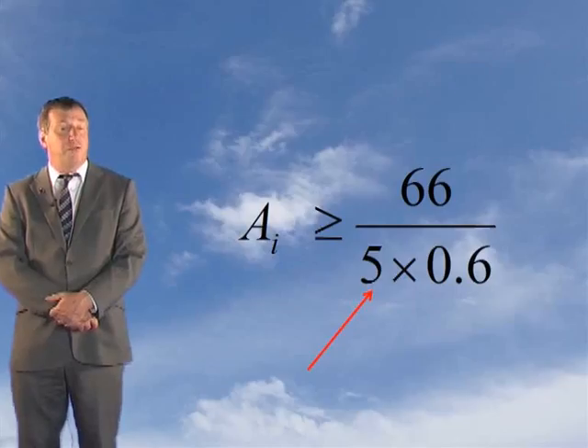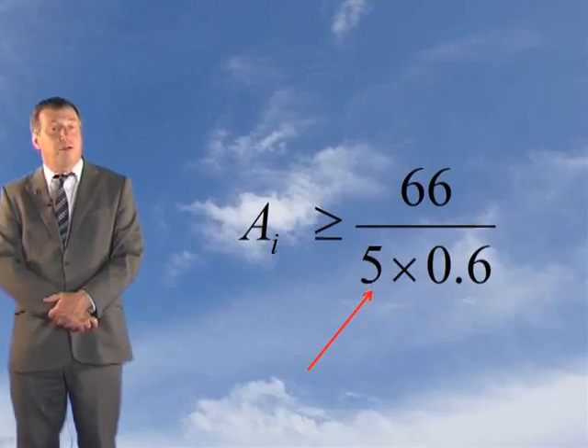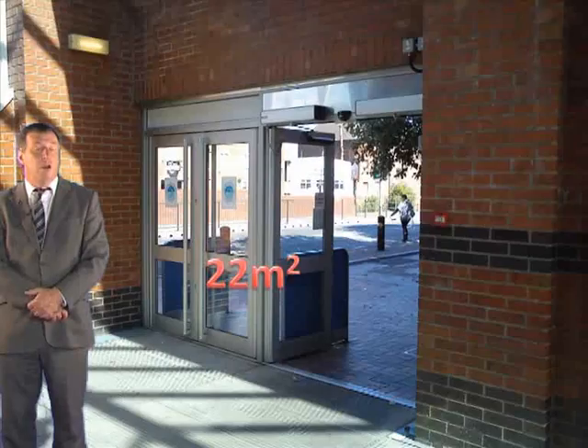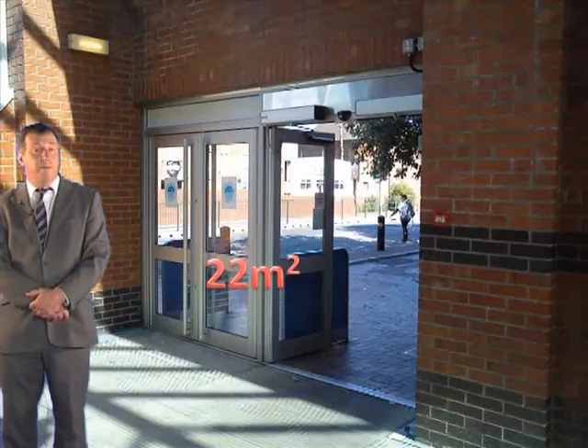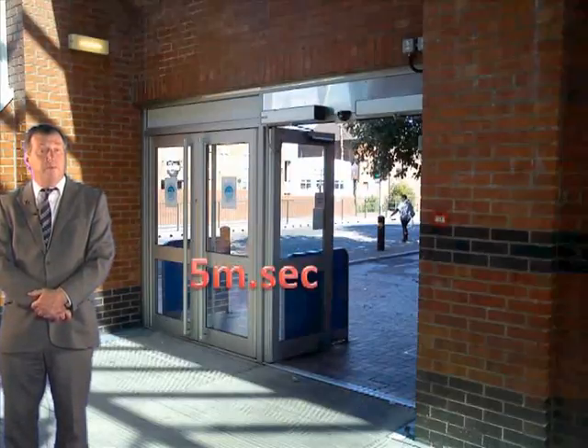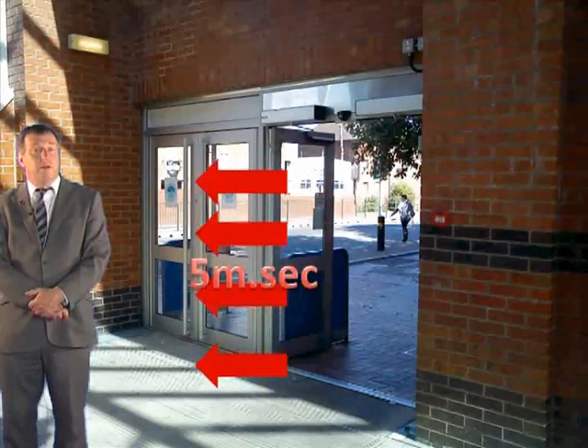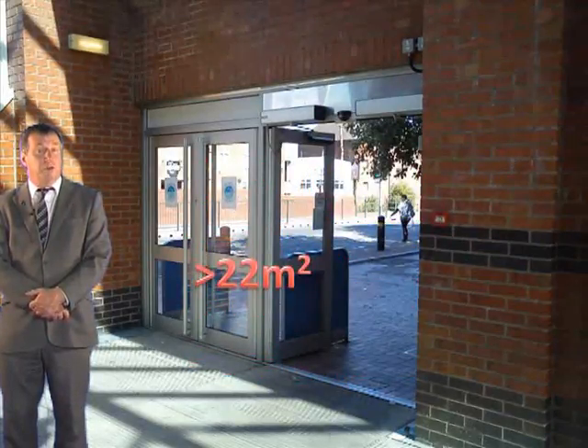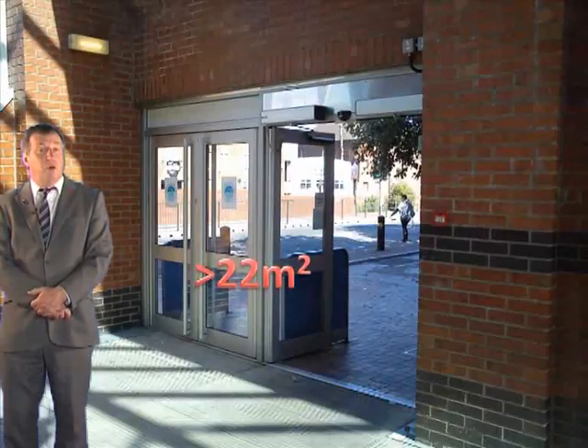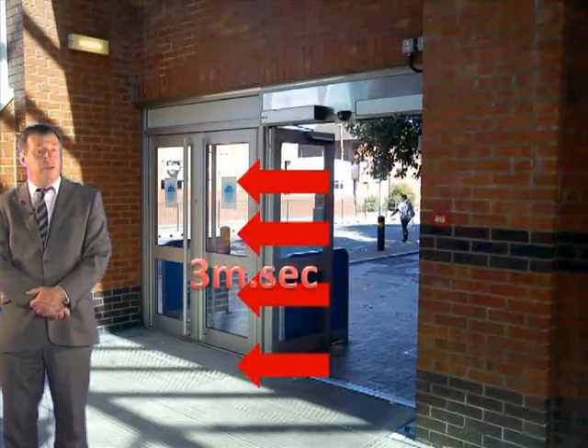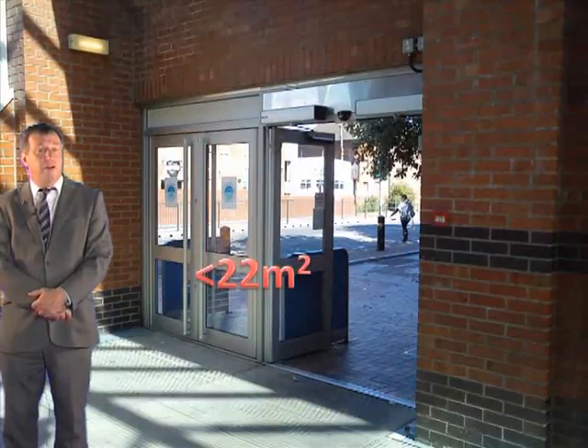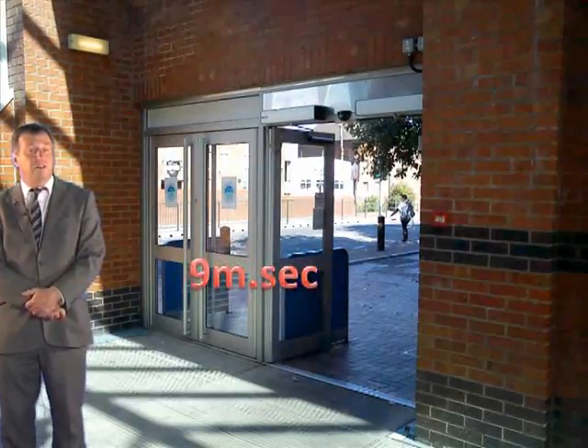We've assumed here that members of the public will be using the building, and so that's why we've used the figure of 5 in the equation for the upper limit for the velocity of the incoming air. What this tells us is that if we have a total of 22 square meters of inlet area, then the replacement air will enter at 5 meters per second. If we have more than 22 square meters of inlet area, then air will enter at a slower velocity, and if we have less than 22 square meters of inlet area, then air will enter at a greater and unacceptable velocity. That concludes the input for this step.